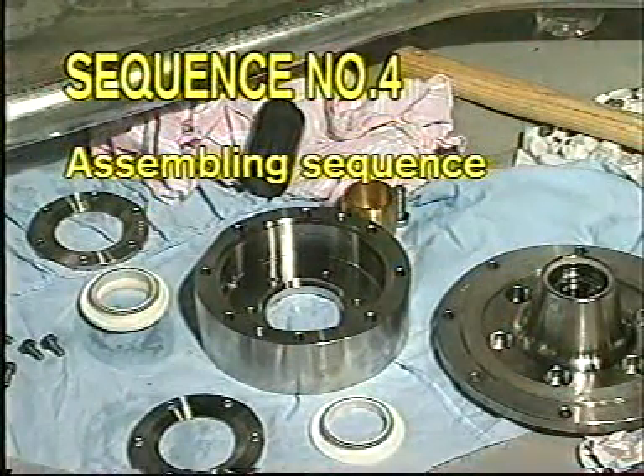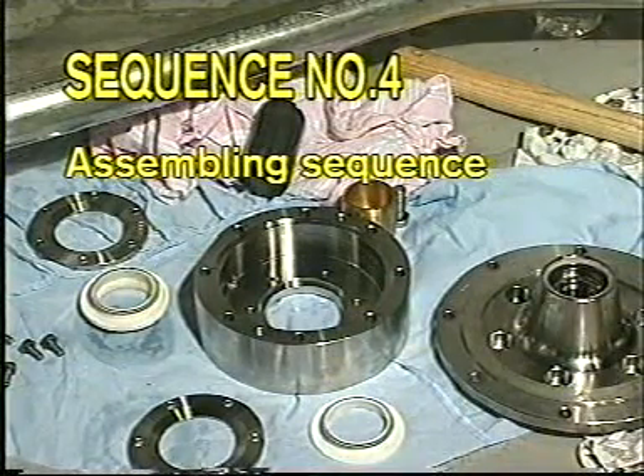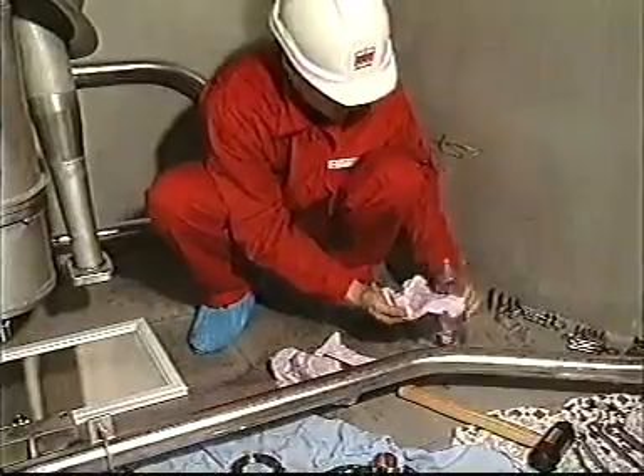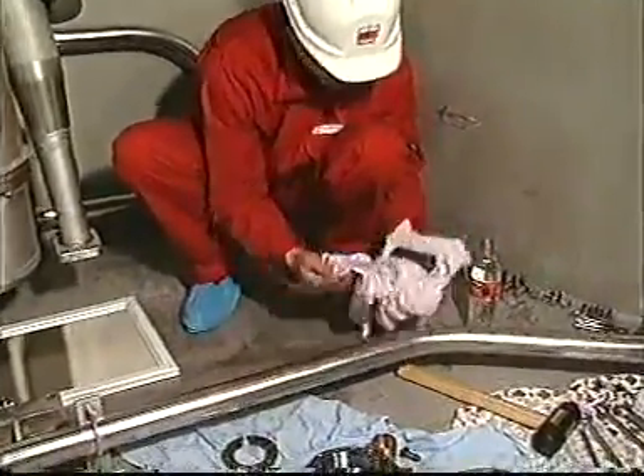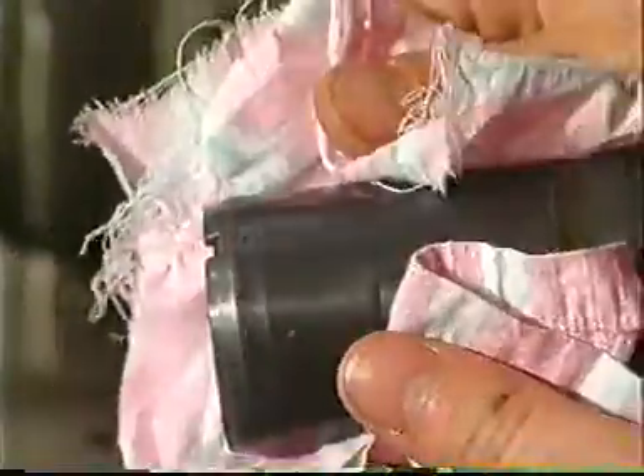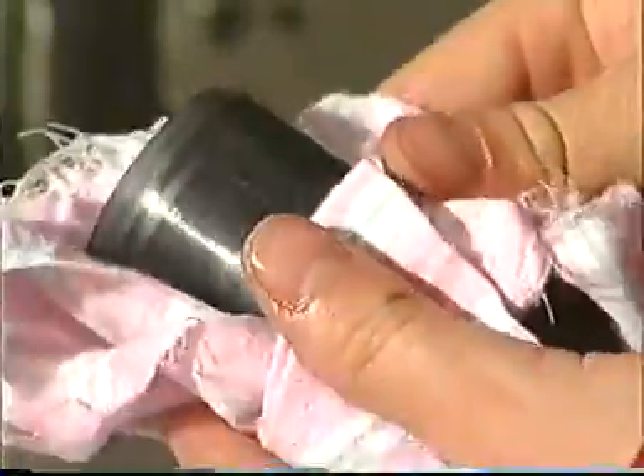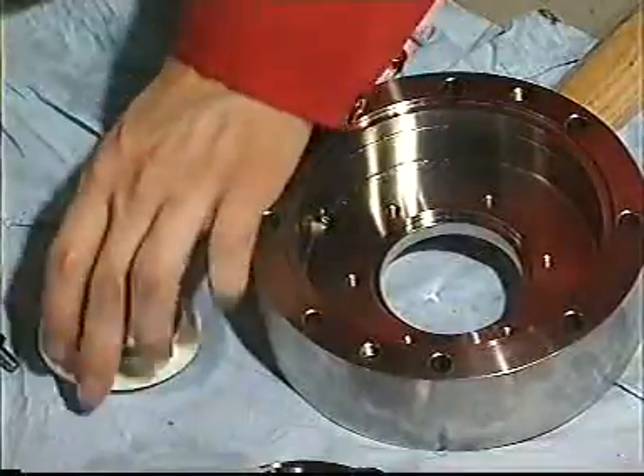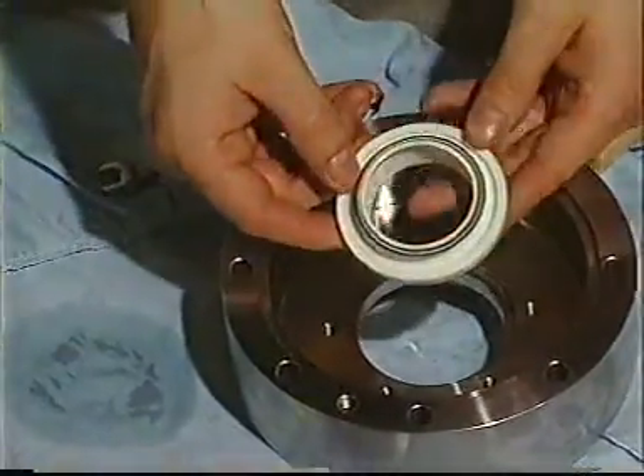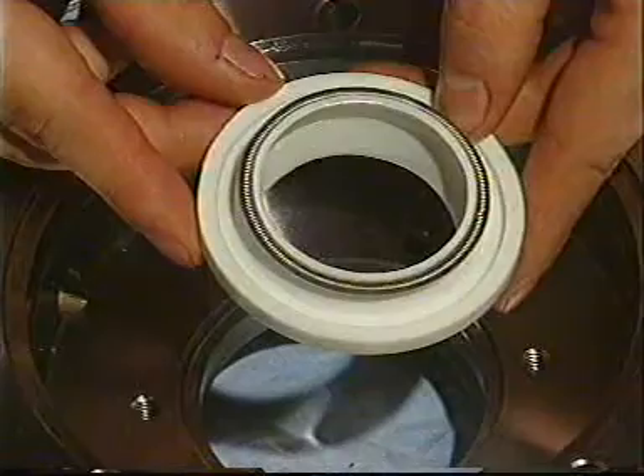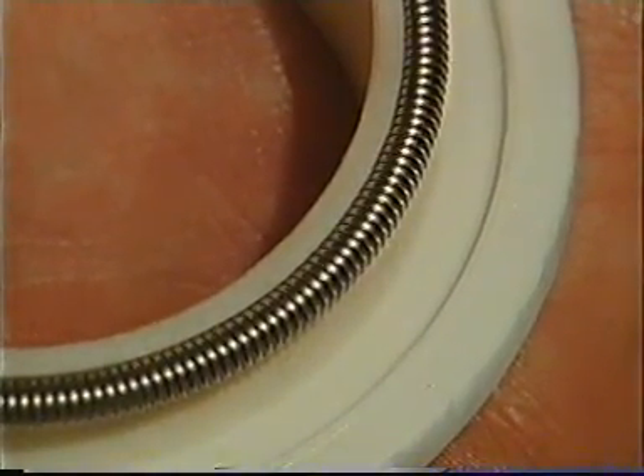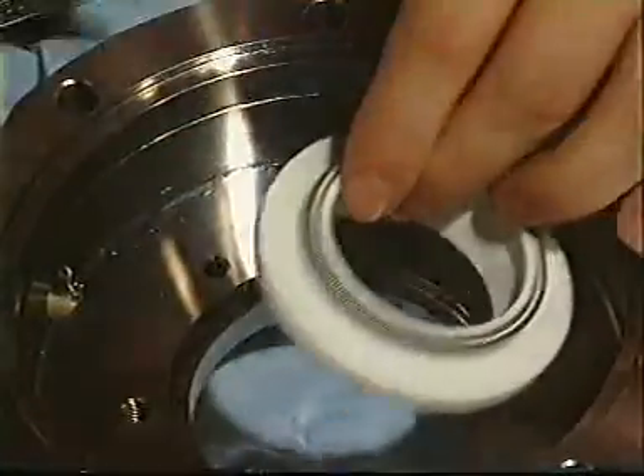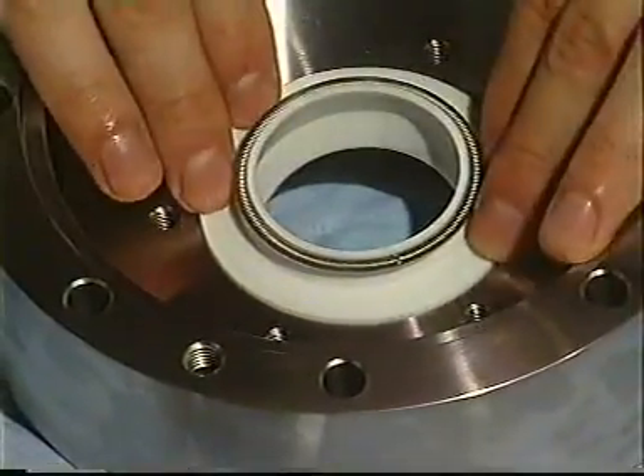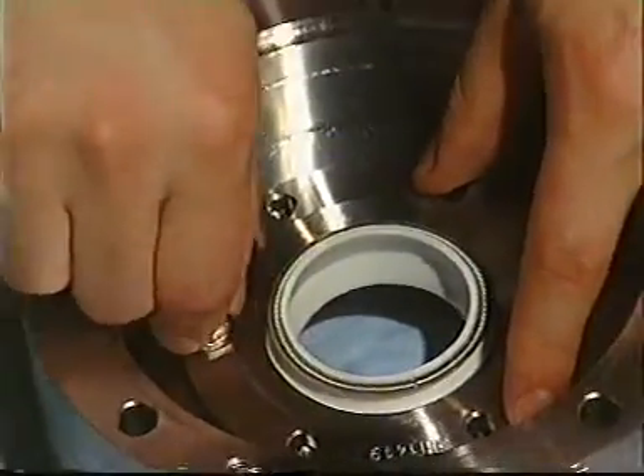Sequence number 4, assembling sequence. All assembling has to be done in reverse according to the dismantling procedure. On this pump design, we will ask you to pay special attention to the ceramic sleeve and to the cargo seals. The ceramic sleeve is equal in either end. To increase lifetime, the sleeve can be turned 180 degrees. The double cargo lip seal must also be installed correctly. On this cargo pump, the 2 springs on the double cargo lip seal are equal. No spring with red marking, but the groove on the seal must be facing down towards the pump impeller.